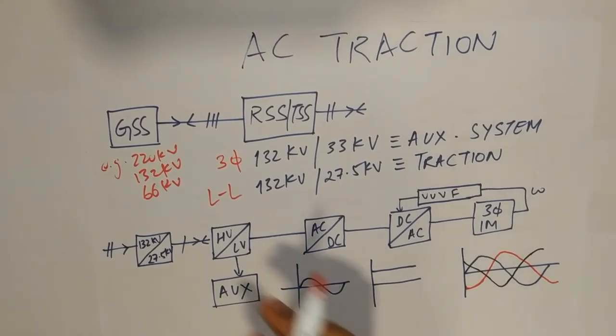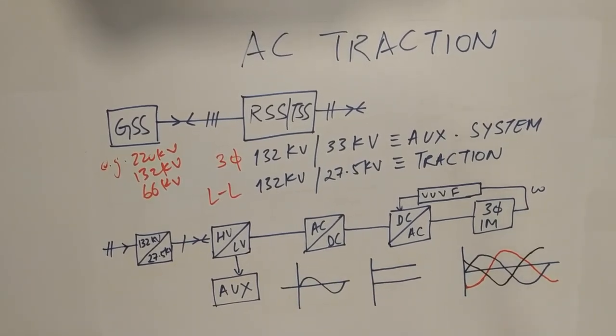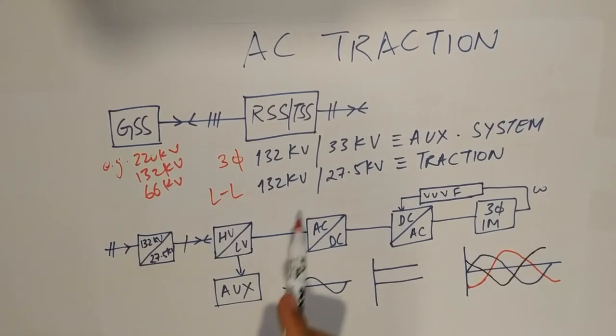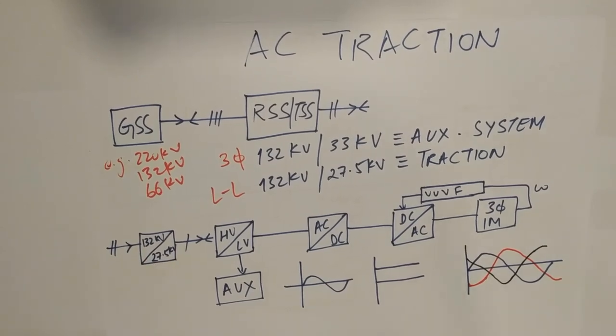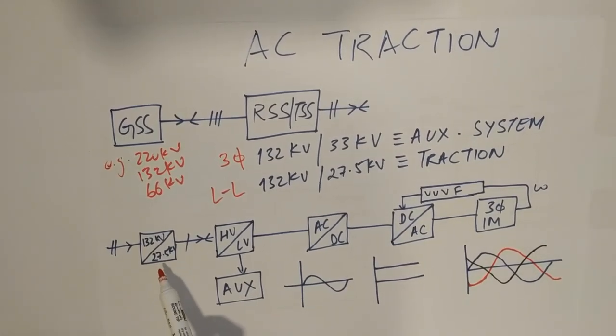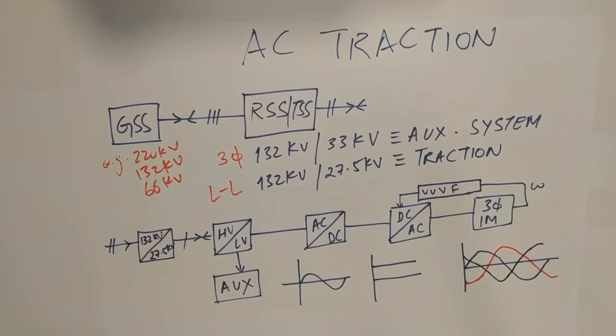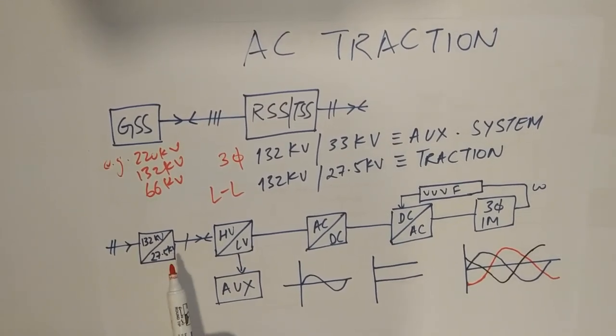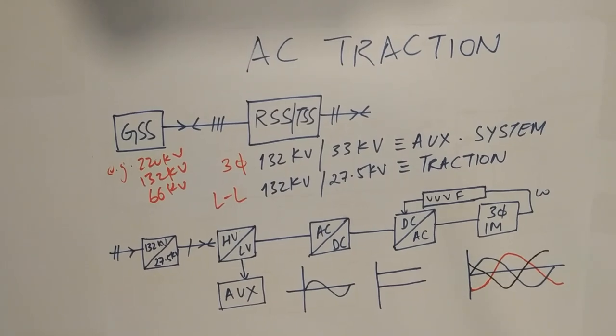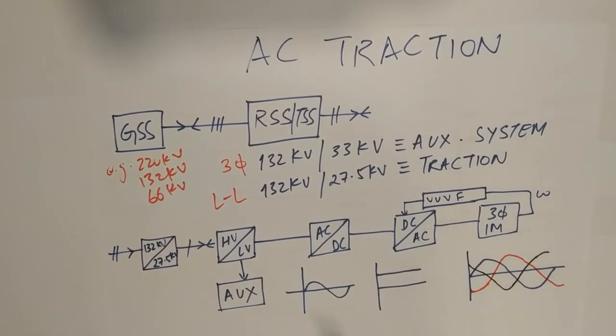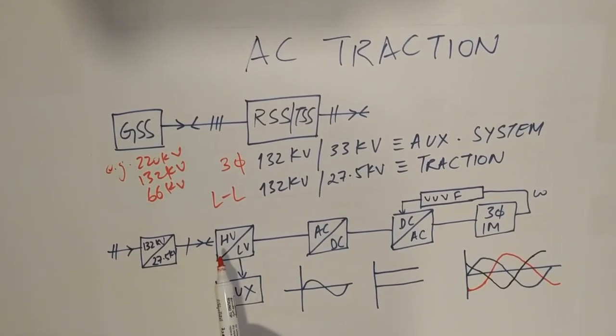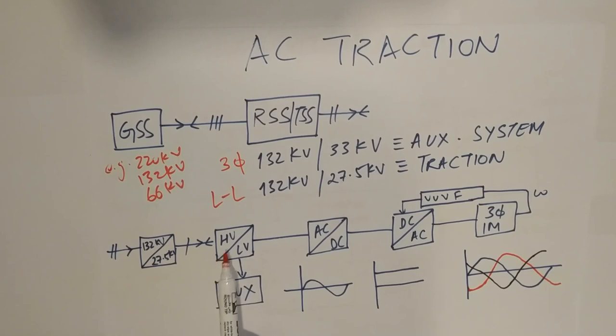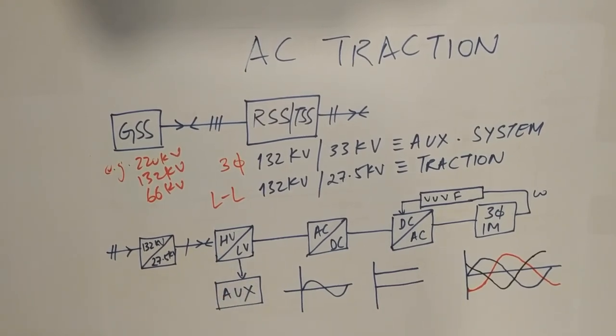So, once we get this 132 KV supply, then this line-to-line supply of 132 KV is converted into 27.5 KV via traction transformer. Then, this 27.5 KV is fed to the overhead contact system and running rails. The train is running between this and then inside the train, this high voltage of 27.5 KV gets converted into a low voltage.